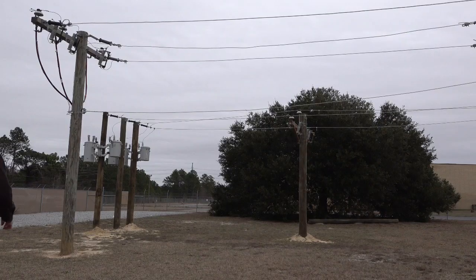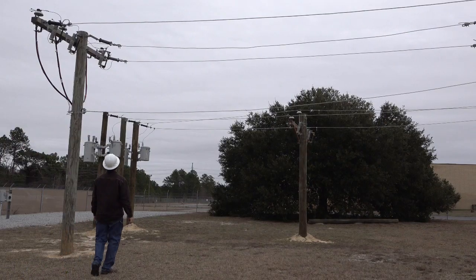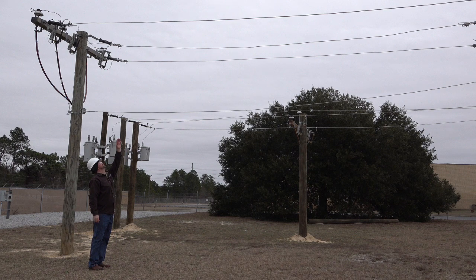In our underground demonstration, we had the VD1000 in the URD switch position. Now I'm standing underneath some of our overhead construction to give you reference of how high it is. This part isn't normal overhead construction. As you notice, the height is only roughly 15 to 16 feet above Earth. But because it is 16 feet above Earth, we need to now flip the VD1000 switch position to the OH position. As the URD switch position is calibrated for roughly 10 feet or lower above Earth, the OH switch position is calibrated at distances greater than that, up to roughly 40 feet above Earth.